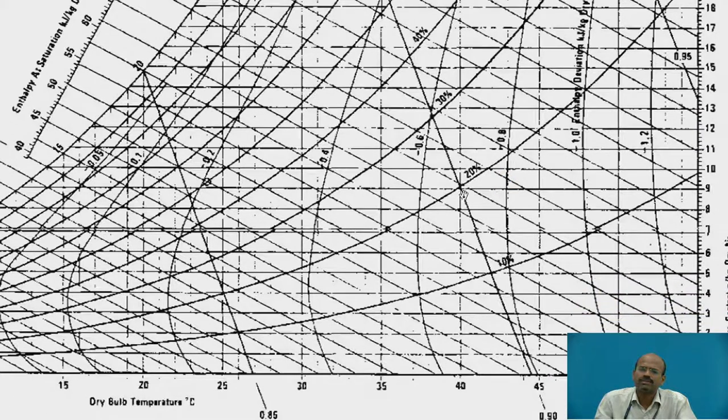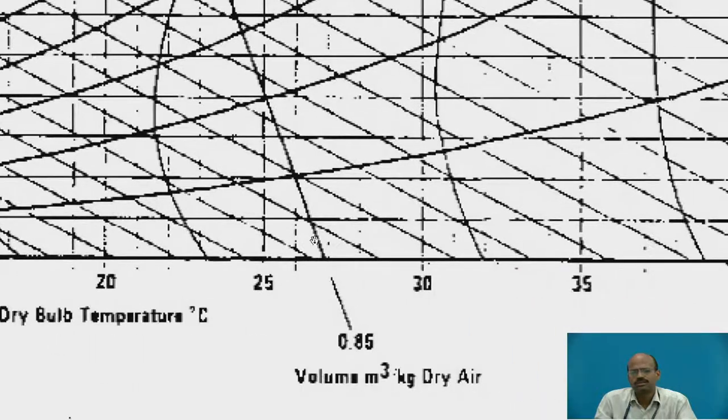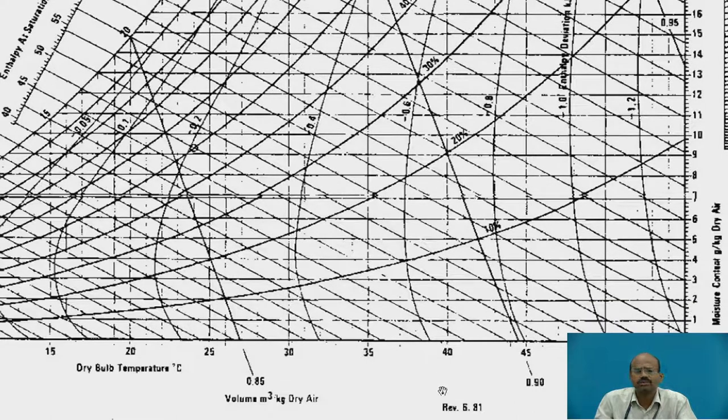Next property is the specific volume. These inclined lines are specific volume lines. This specific volume line is having 0.85 meter cube of volume per kg of dry air. If it lies in between these two constant specific volume lines, by using the compass, you have to divide this distance into equal parts and proportionate value will be getting from the psychrometric chart, because this is the graphical method.